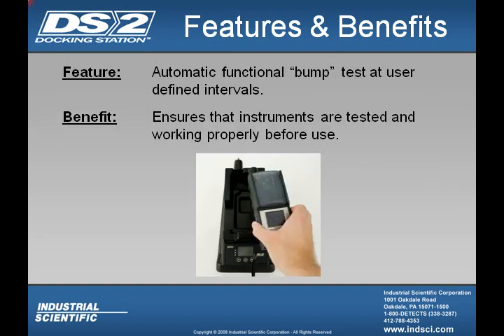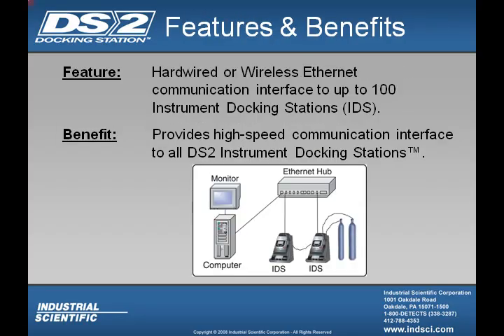Another feature of your docking station is automatic bump testing at user-definable intervals. And what this will do is ensure the instruments are tested and working properly before they're put into use that day. Also, you have hardwire or wireless Ethernet communications, which allows you to communicate with up to 100 instrument docking stations simultaneously. And what this will do is provide a high-speed communication interface to all docking stations.